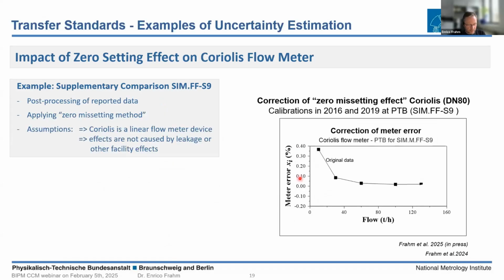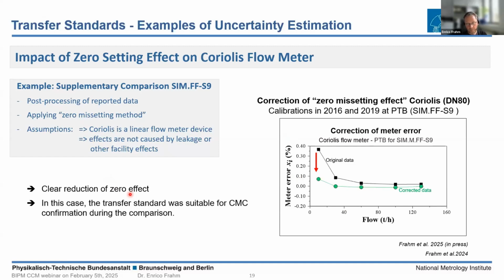But under special assumptions, it was possible to post-process the Coriolis data by a newly introduced zero missetting method. And if this method was applied, the zero effect was clearly reduced, as well as the meter uncertainty in the lower flow range. In this case, the transfer standard was suitable for CMC confirmation during the comparison.